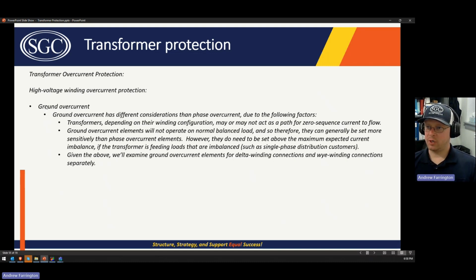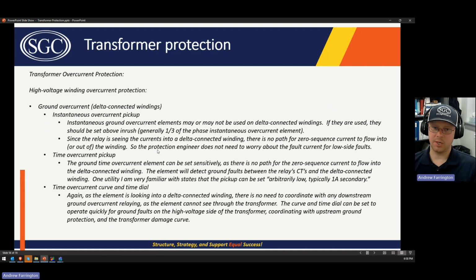High voltage winding ground over current: this is talking about how there are different factors. Please review this. If it's a delta connected winding, basically the high side ground over current instantaneous element, you just need to set it above inrush, which is typically estimated to be 1/3 of the amount of inrush you'd see for a phase element. So if you set the phase instantaneous element to consider 12 times the OA rating of the transformer, then you might set the ground instantaneous element to 4 times the OA rating of the transformer.